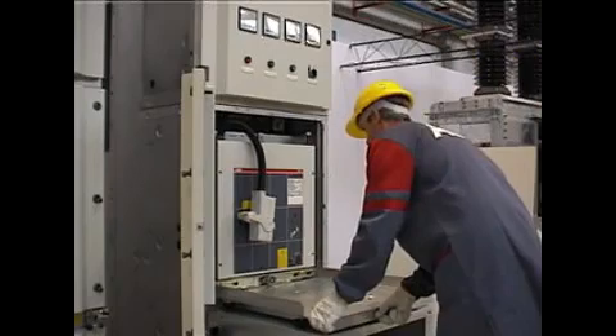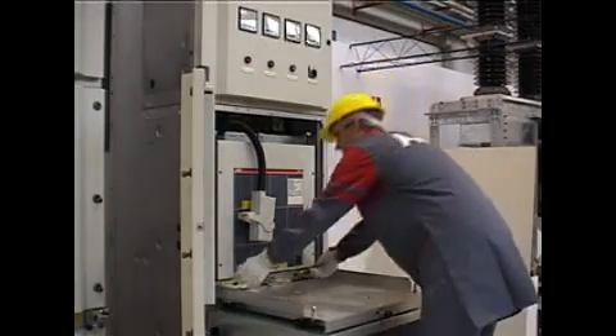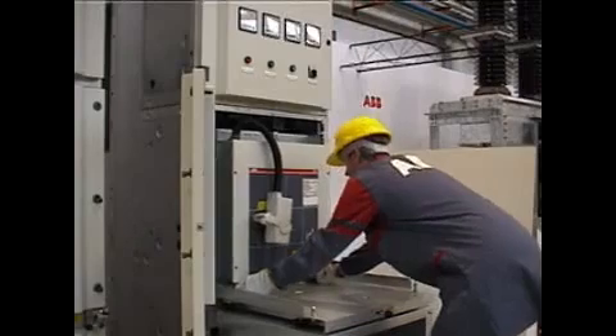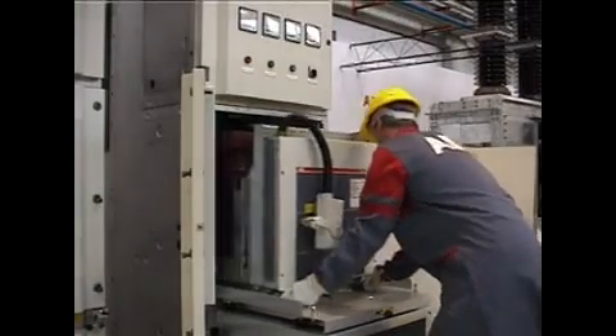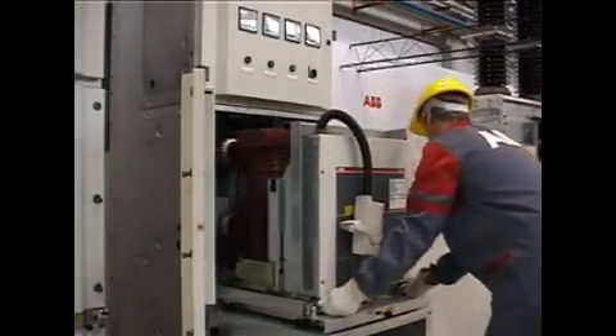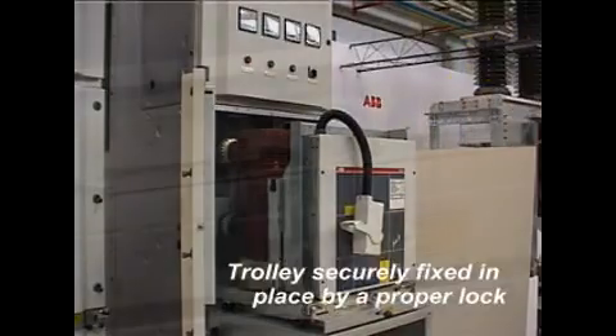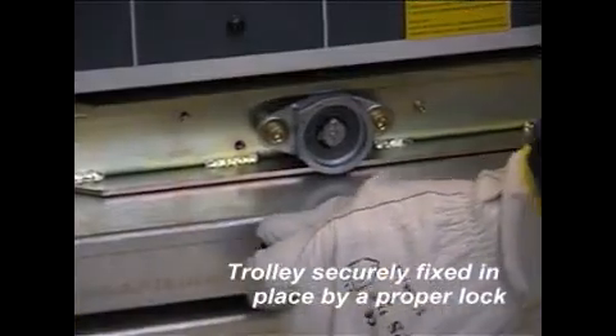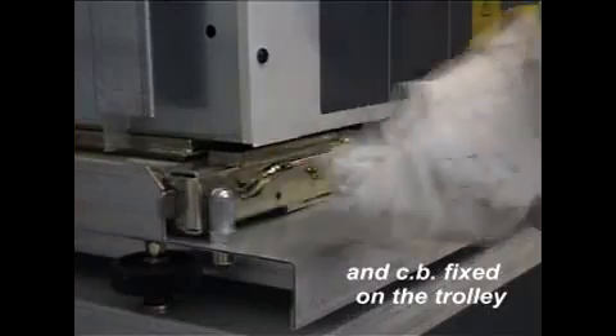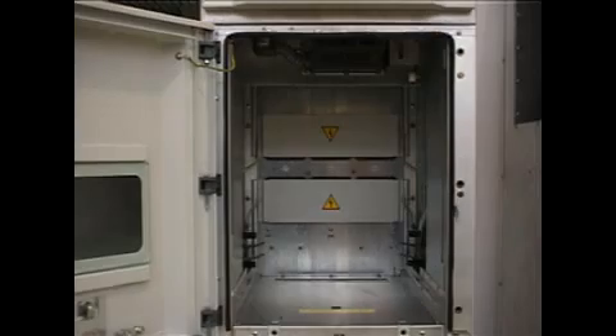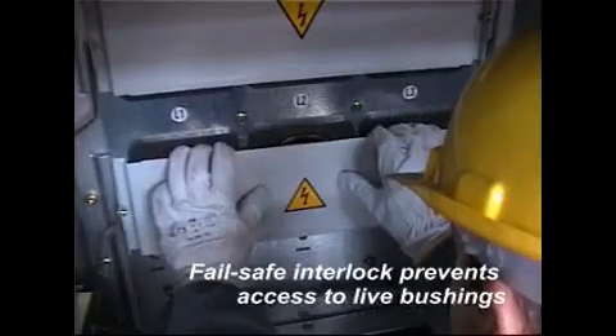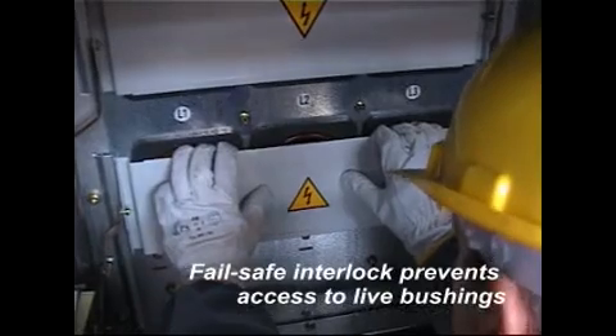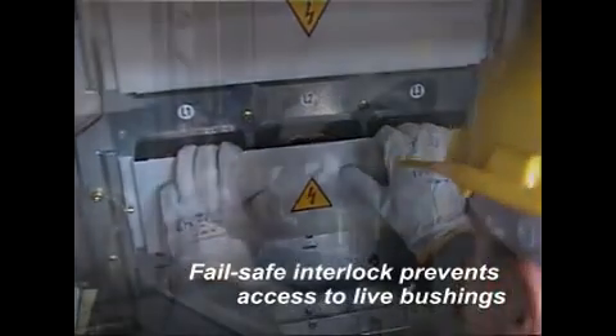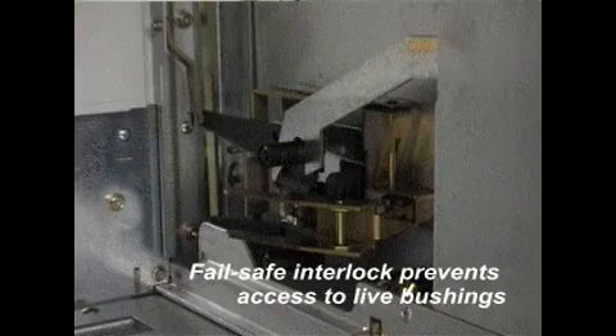If we remove the plug, the circuit breaker can be extracted from the cubicle by means of a proper trolley which can be safely secured to the panel during the travel, and that is fitted with proper locks to make sure that the breaker will remain in place when the trolley is moved away. We are now showing you the fail-safe interlock which prevents the operator from getting access to the live bushings by removing shutters.